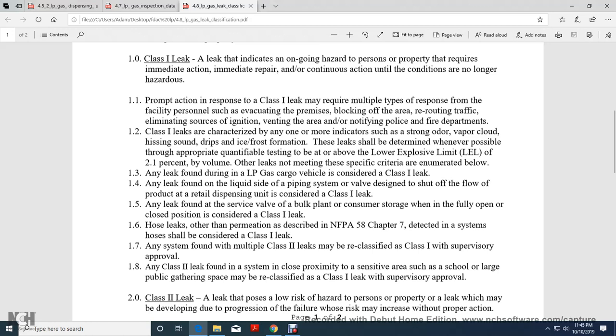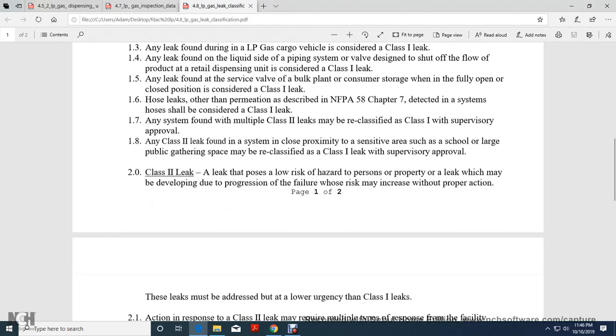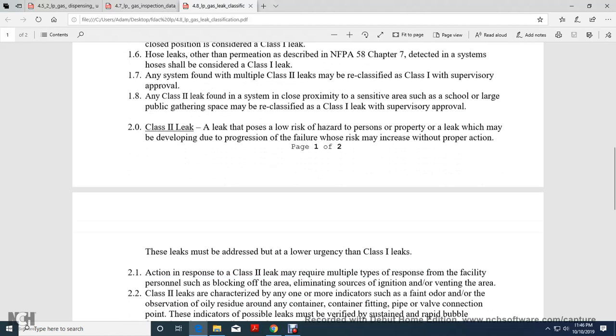Any leak found on the service valve of the bulk plant or consumer storage in a fully open or closed position is considered a Class 1 leak. Hose leaks or other permeation described in National Fire Protection Association 58, Chapter 7 — the detail of the detected system hoses — are considered a Class 1 leak. Any system found with multiple Class 2 leaks may be reclassified as a Class 1 leak with supervisor approval. Class 2 leaks found in a system in close proximity to a sensitive area such as a school or large public gathering place may be reclassified as a Class 1 leak with supervisor approval.